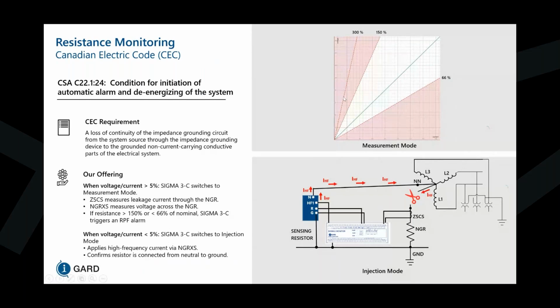If it's beyond 150% or below 66%, we can indicate a fault condition. So this measurement mode is only active when the voltage and current is above 5% of the threshold. When it's below 5%, we're still injecting this high frequency and DC-based injection method.